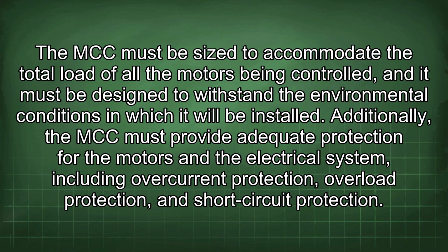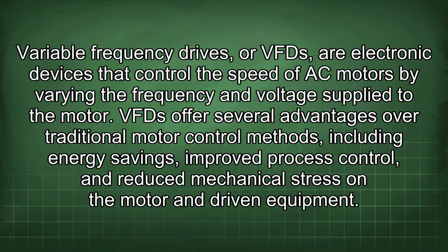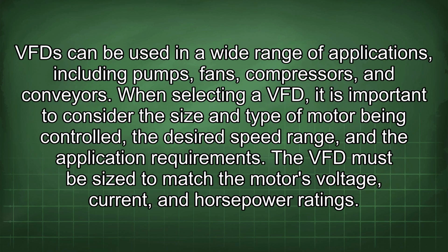short-circuit protection. Variable frequency drives, or VFDs, are electronic devices that control the speed of AC motors by varying the frequency and voltage supplied to the motor. VFDs offer several advantages over traditional motor control methods, including energy savings, improved process control, and reduced mechanical stress on the motor and driven equipment. VFDs can be used in a wide range of applications, including pumps, fans, compressors, and conveyors.